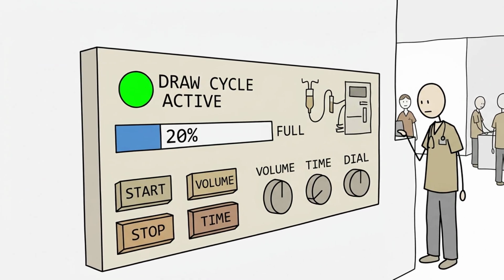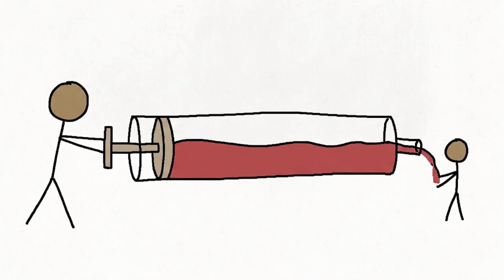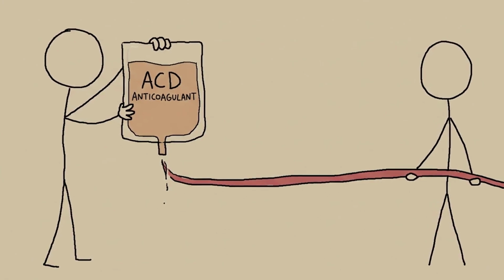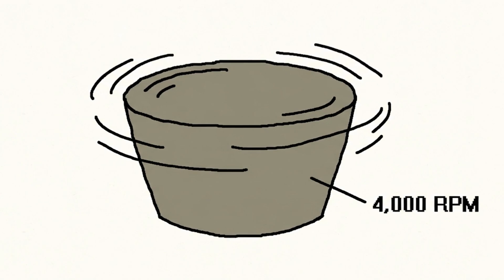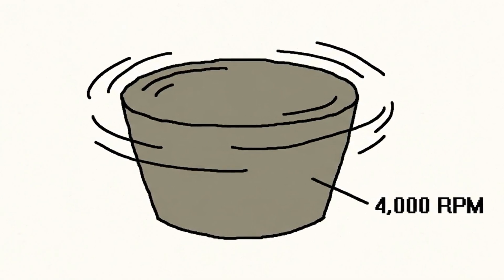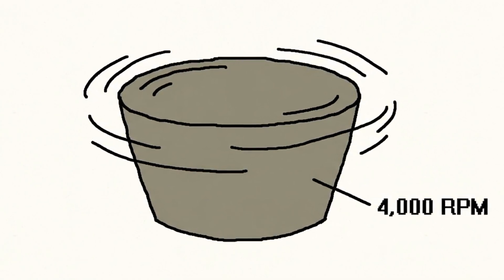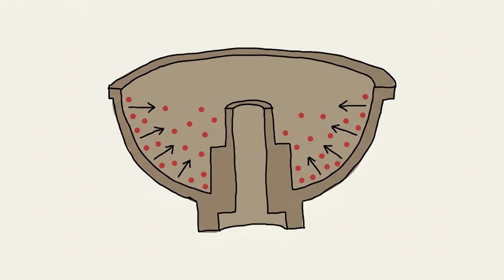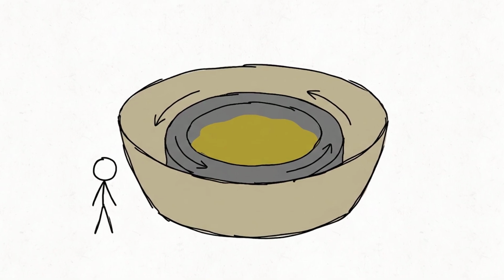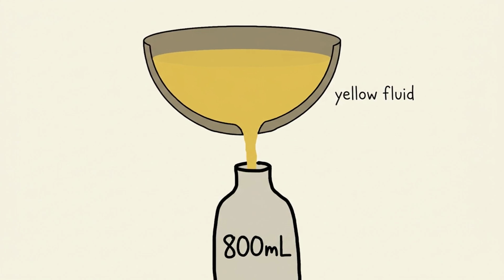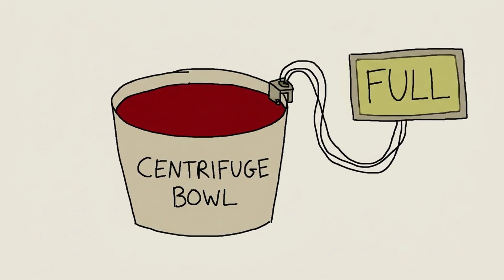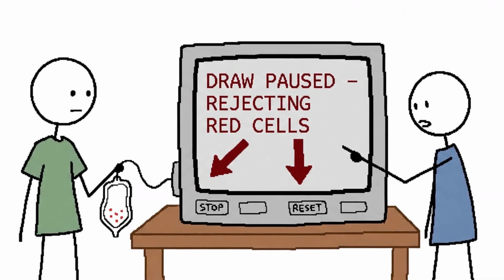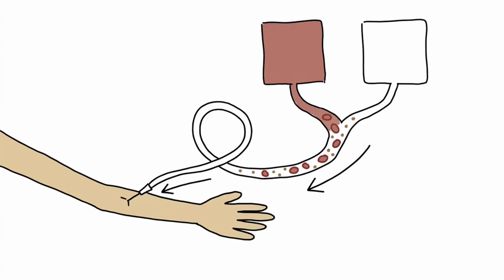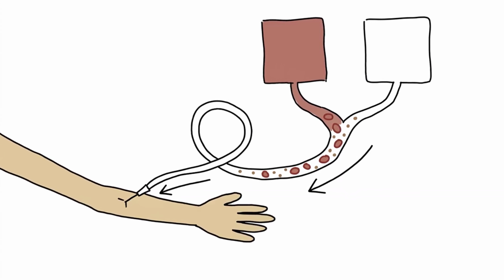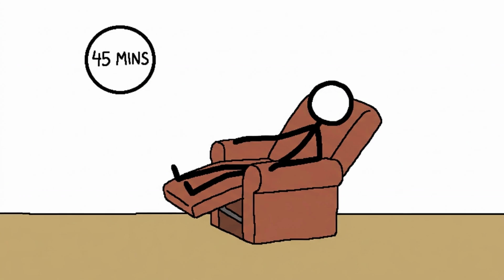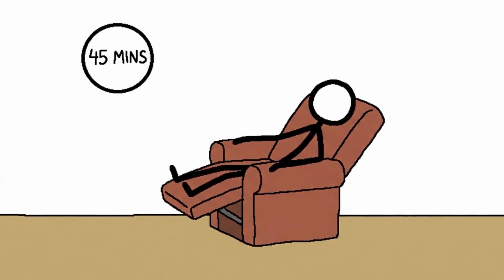The machine begins the automated draw cycle. Whole blood is drawn from the arm, mixing with anticoagulant citrate dextrose to prevent clotting inside the sterile tubing. The blood enters the spinning centrifuge bowl at high speeds, ranging from 3,000 to 5,000 revolutions per minute. Dense red blood cells push outward against the bowl wall, while lighter, amber-colored plasma floats to the center and siphons into an 800 milliliter collection bottle. Once the bowl fills with red blood cells, the machine automatically pauses the draw cycle and reverses flow, pumping the red blood cells back into the donor along with 500 milliliters of sterile normal saline solution. The entire automated process takes 45 to 60 minutes per donor.